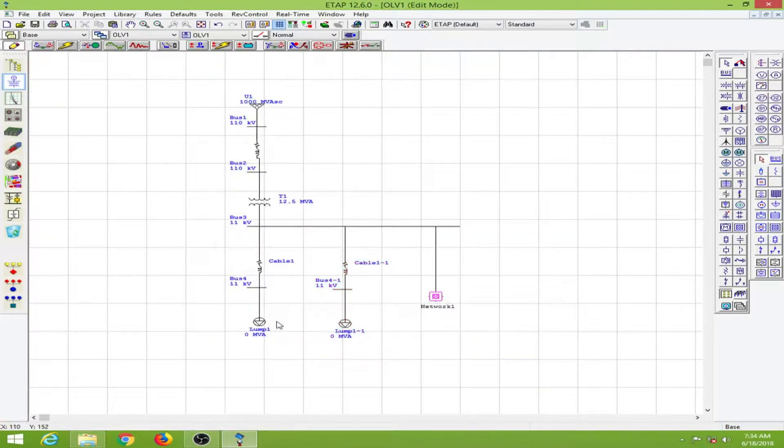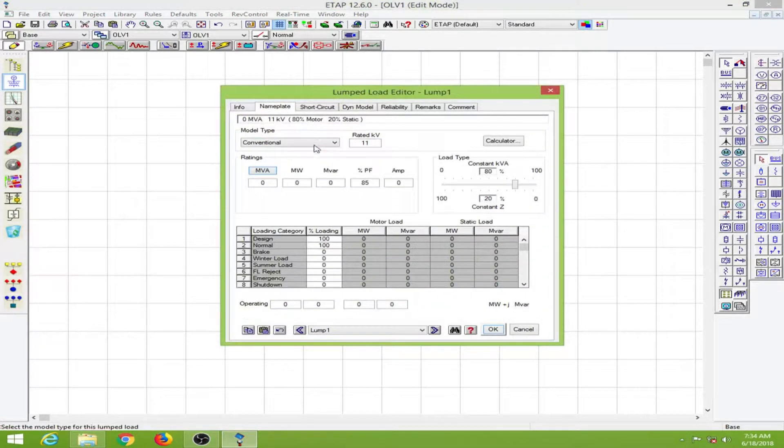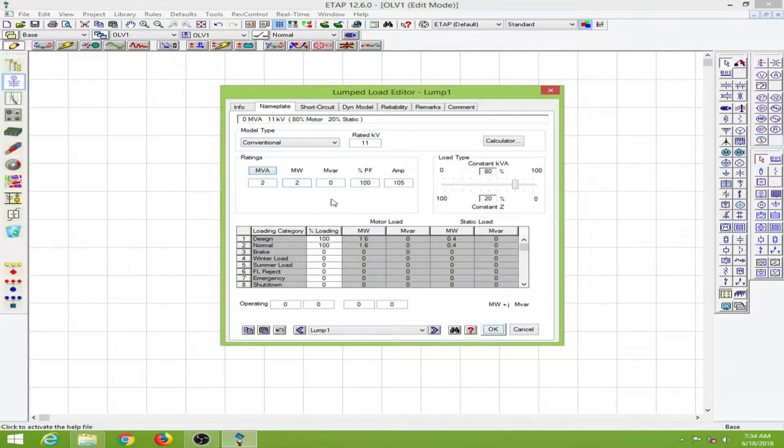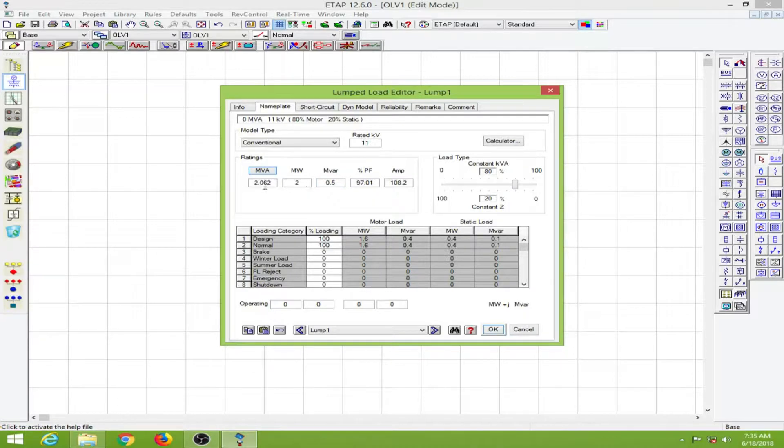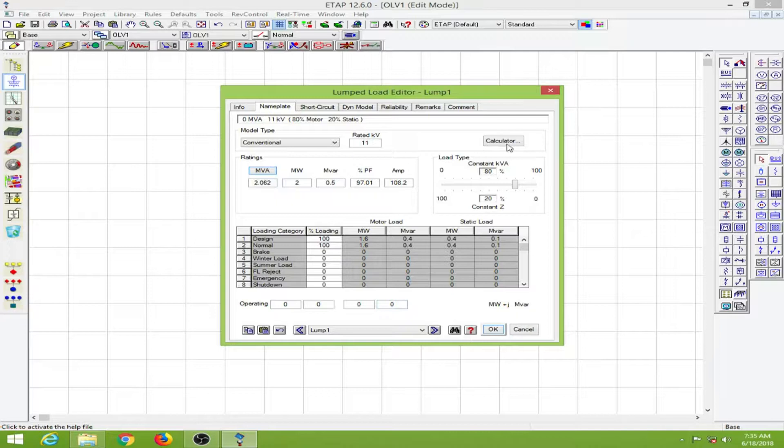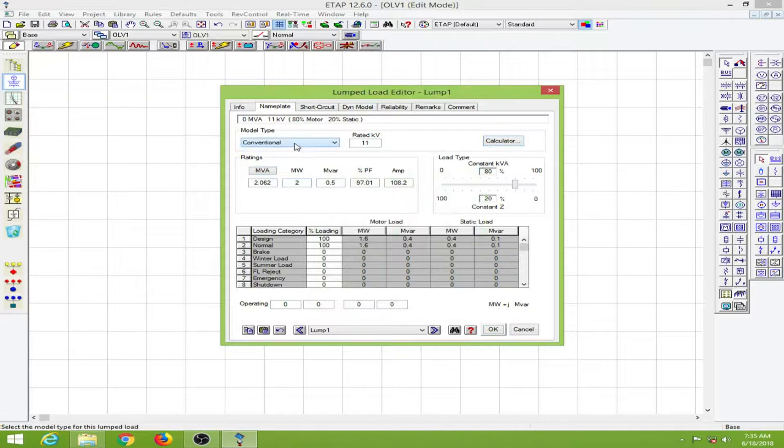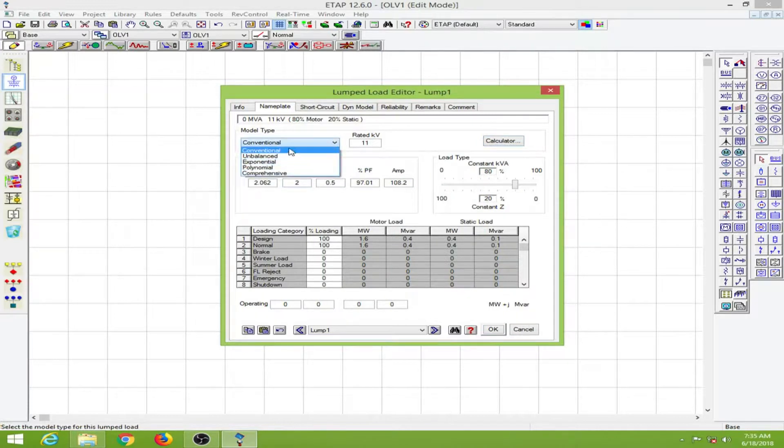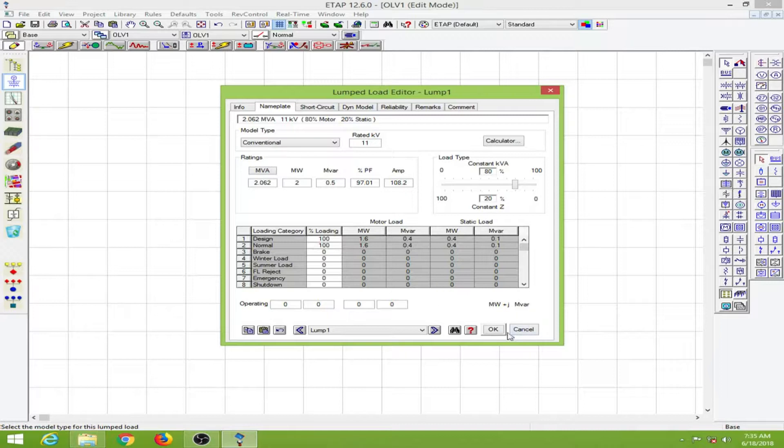Now the lump load. I will provide a 2 megawatt load with 0.5 MVAR. That automatically puts the power factor at 97 percent and the MVA is calculated. You can use this calculator also. We can change the model type. This is all the right values, so I will click OK.